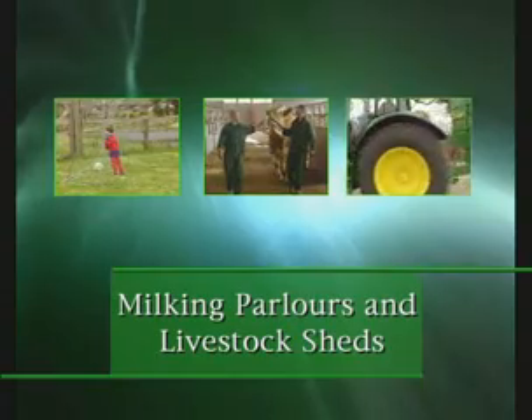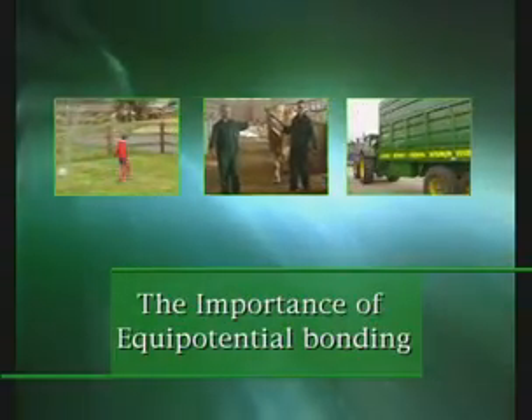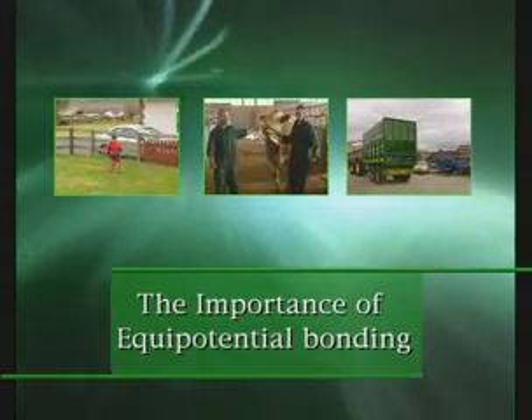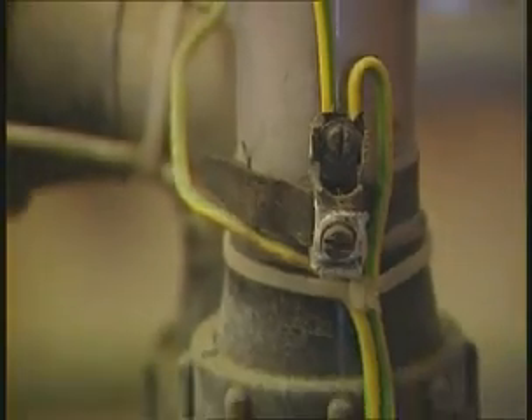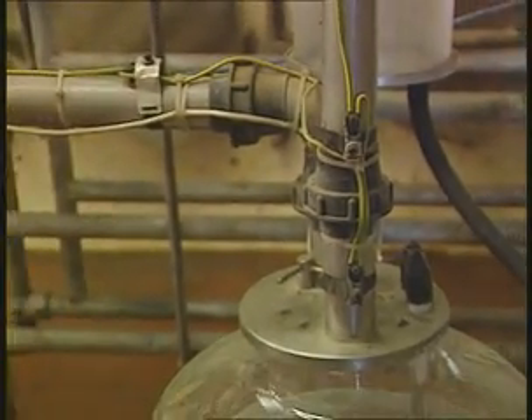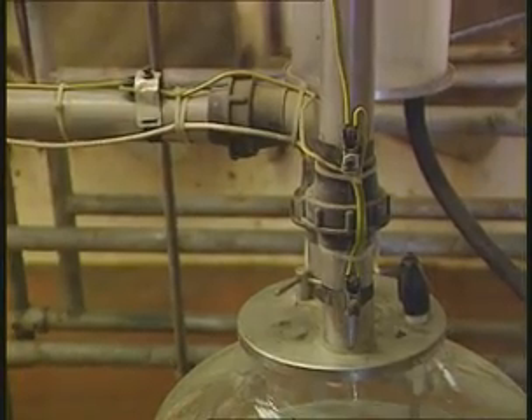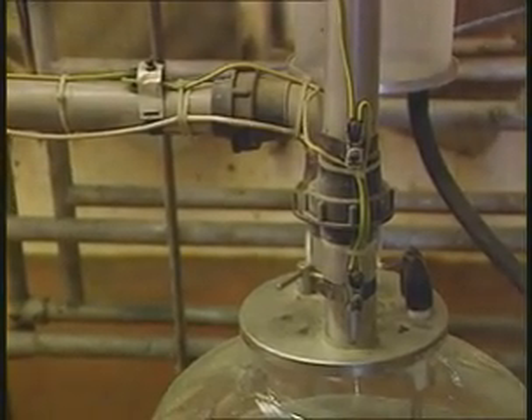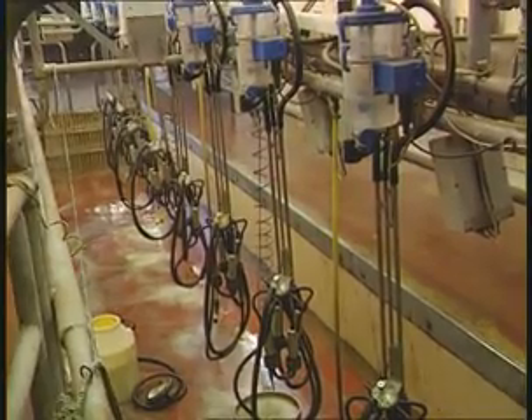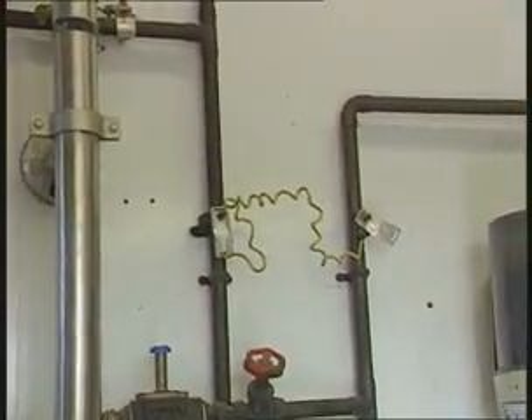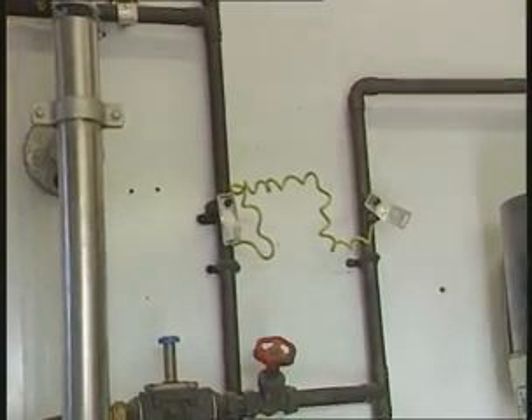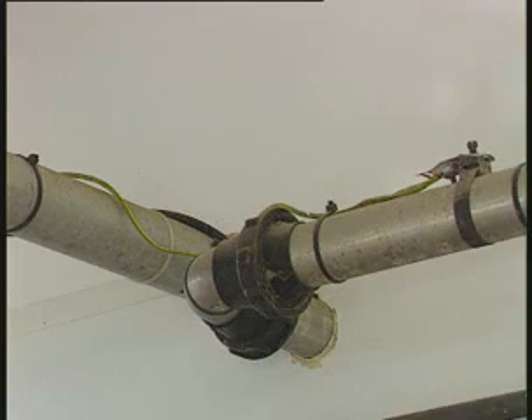Milking parlours and livestock sheds. The importance of equipotential bonding. Because cattle are even more sensitive to electrical shock than humans, it is crucially important to minimize voltage differences which can occur between metal components and earth in locations such as milking parlours and livestock sheds. The way this is done is through equipotential bonding. What this means is that every part of the exposed metalwork is electrically bonded together and bonded to earth so that there are no potentially dangerous voltage differences to cause electric shock.